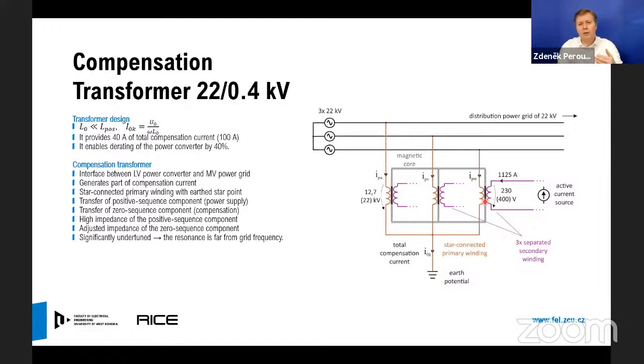It means that we are able to provide 40% of the compensation current without any necessary intervention by the power converter, which makes it possible to save 30% of the silicon in the converter. And it leads to significant cost savings. The very important feature of the configuration is also that we operate the system significantly undertuned. It means that the resonant frequency given by the zero sequence impedance of the transformer acting with the grid capacitance is significantly below the operating frequency of the grid, which has positive impacts in the reduced asymmetry of the grid and reduced zero sequence component of the voltage.